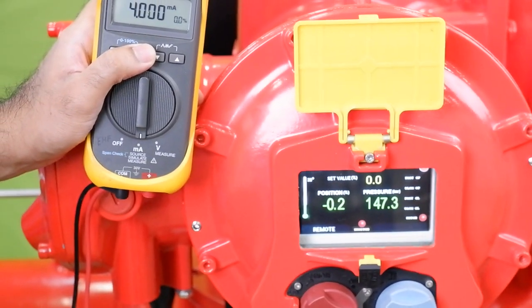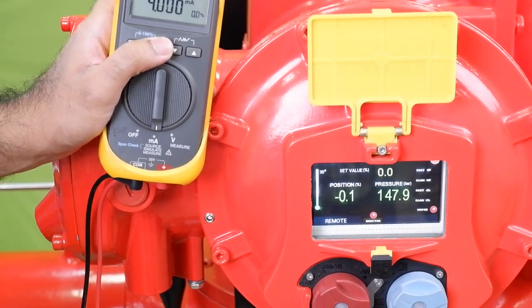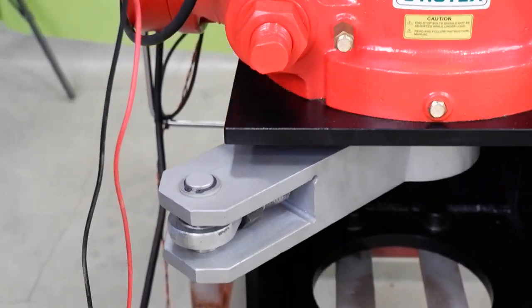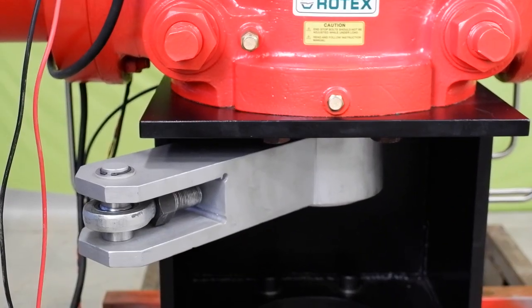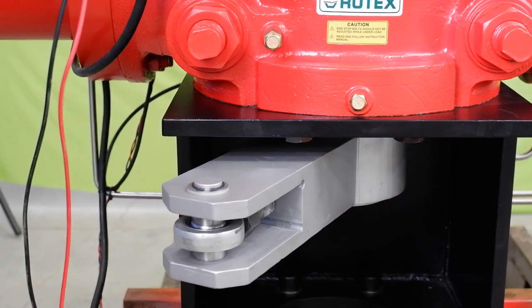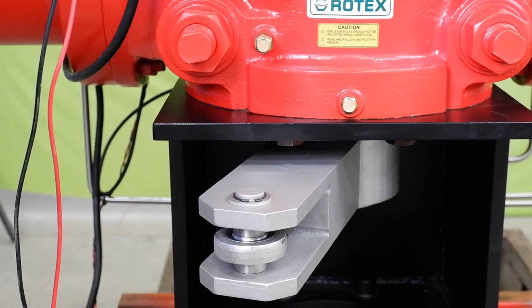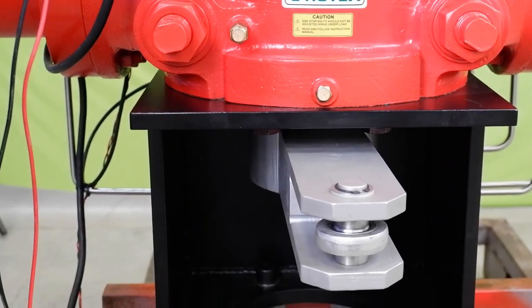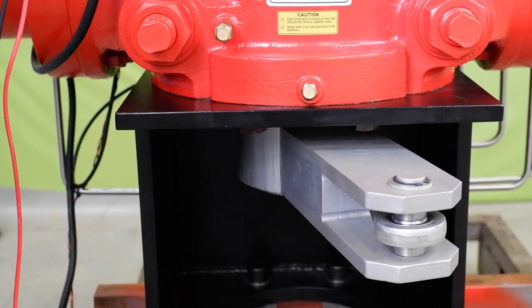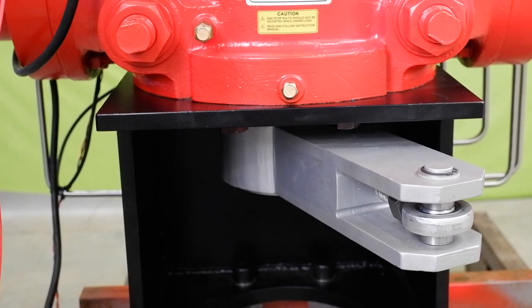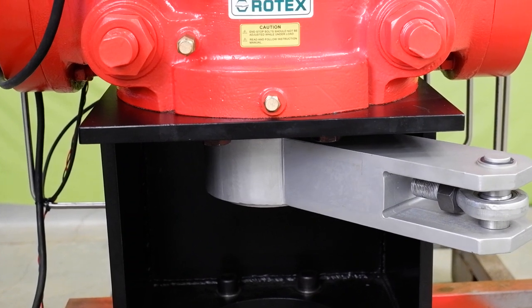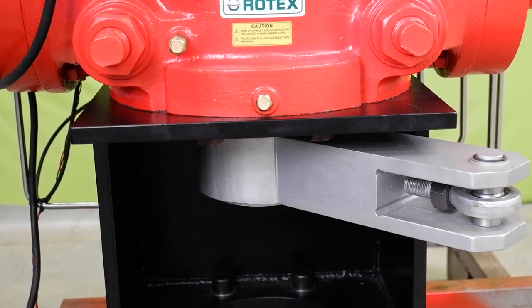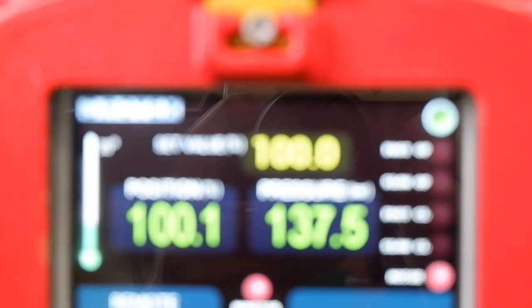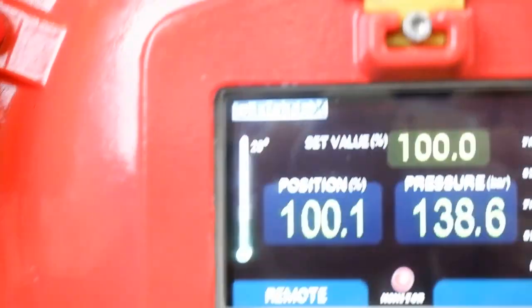Now we will see the valve position changing with respect to the remote input signal. It is now fully closed, as you can see. Now I will change the input signal to 25%. The valve is open 25%. Now the valve is open 50%. Now the valve is open 75%. And now the valve is fully opened. Now this open condition is also displayed both on the TFT display and the mechanical dome switch provided on the EHF head.